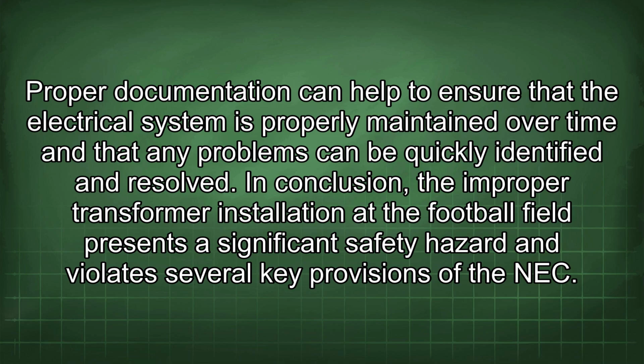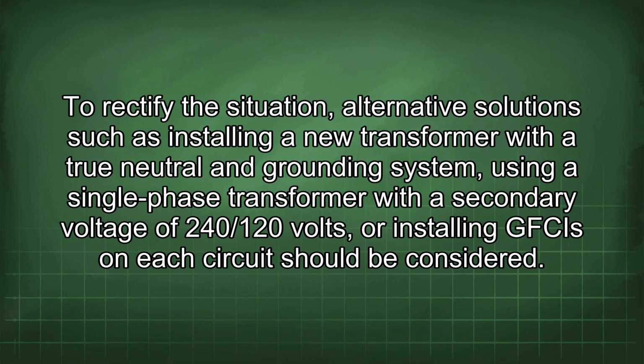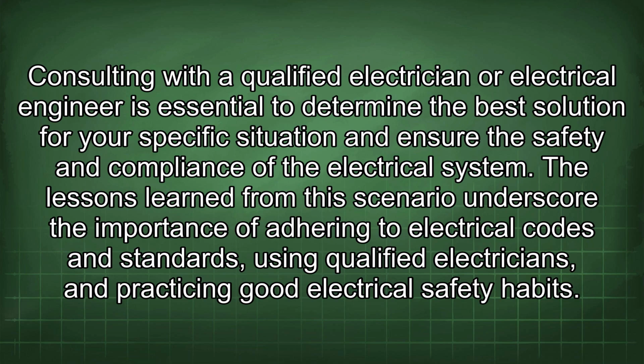In conclusion, the improper transformer installation at the football field presents a significant safety hazard and violates several key provisions of the NEC. To rectify the situation, alternative solutions such as installing a new transformer with a true neutral and grounding system using a single-phase transformer with a secondary voltage of 240/120 volts, or installing GFCIs on each circuit should be considered. Consulting with a qualified electrician or electrical engineer is essential to determine the best solution for your specific situation and ensure the safety and compliance of the electrical system.